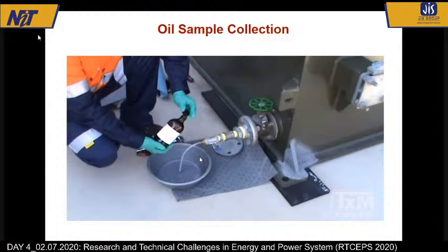Now oil is one of the important insulations. This photograph shows what is called the oil drain valve. All our young participants should see a real life transformer; these oil drain valves are mandatory. Generally this green valve will be closed so oil doesn't come out, but if we want an oil sample, it's simple: we open this valve like a tap, collect the oil, and close it again. So we don't have to switch off the transformer; it can keep running while we collect the oil sample. This is extremely important from our monitoring point of view.